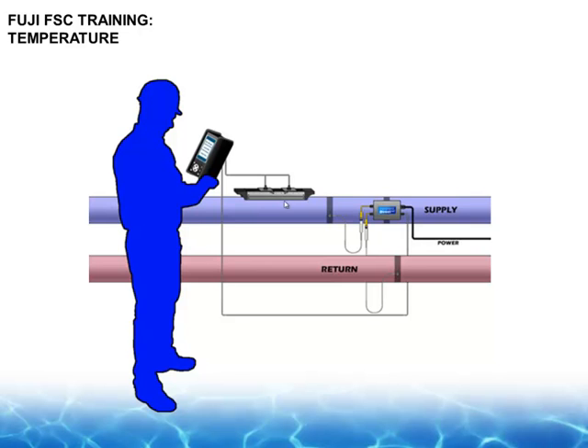We're monitoring flow on the supply. And then we're going to monitor temperature on the supply. And we're going to clamp the sensor on the outside of the pipe. Then we're also going to monitor temperature on the return line. And the equation is, we need to know flow and differential of temperature to calculate your BTU. And guess what? All this data goes back to the Portaflow-C logger. So it's going to log flow, temperature 1, temperature 2, and calculate the BTU. So when you download everything, you have all the data that you ever possibly wanted to get.